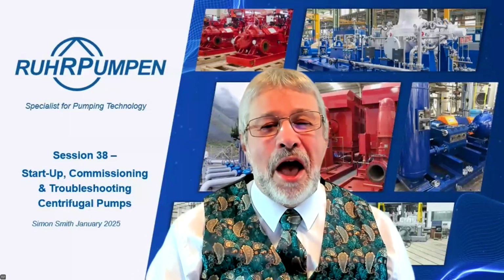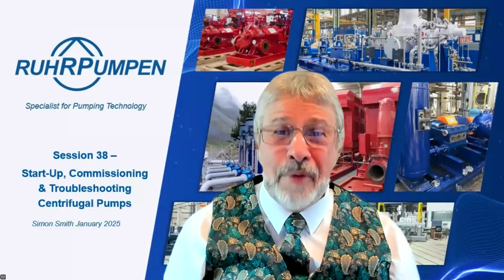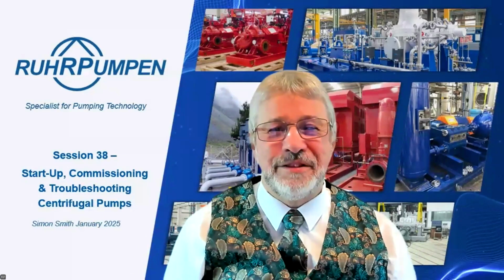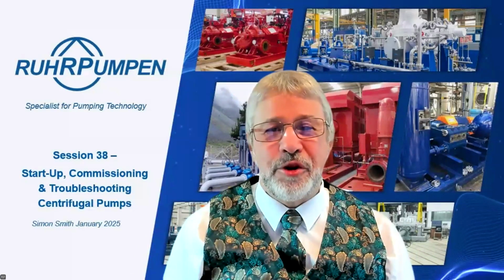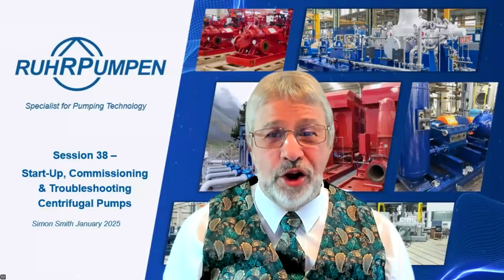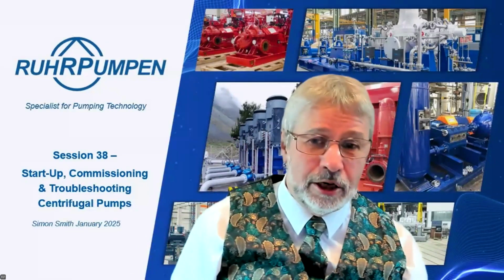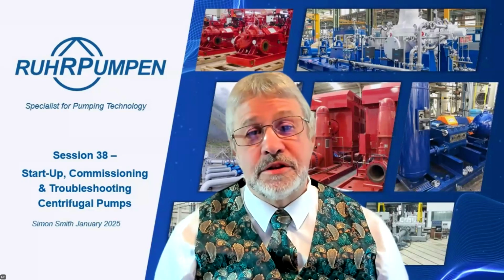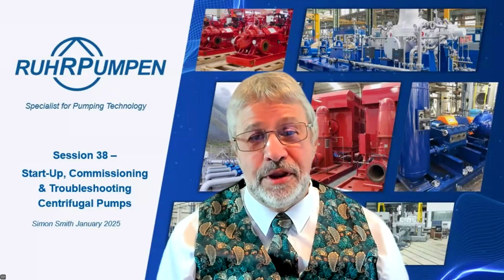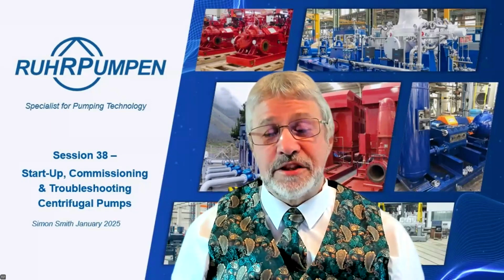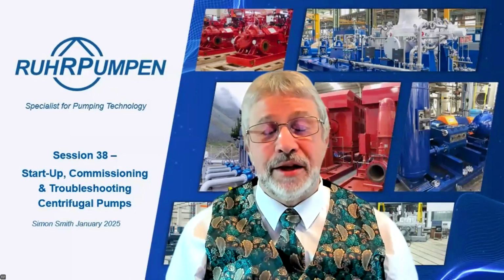Gabriella Manenti, how can too much oil provide high temperature on a thrust bearing? It does. I had a great story from my pump guru when I was learning pumps. He said he went onto a refinery one day because the pump was running hot, the bearings were running hot, and he looked at the oil level and he was chatting away with the maintenance engineers and he got his wrench out and he opened up the drain connection and stood there chatting away to the guys while oil was pouring down into the drip pan.